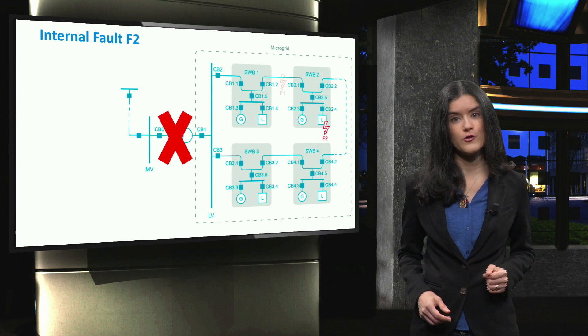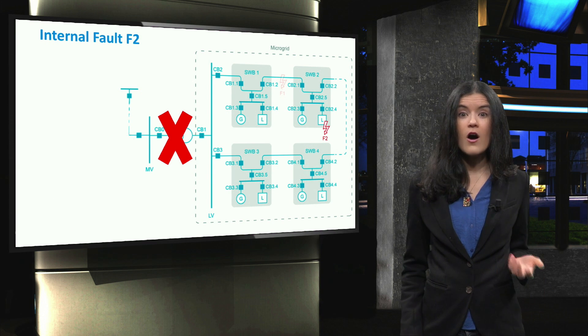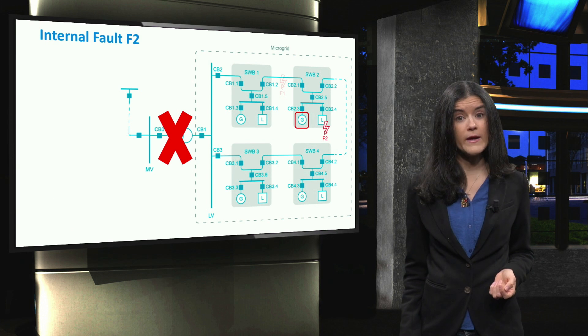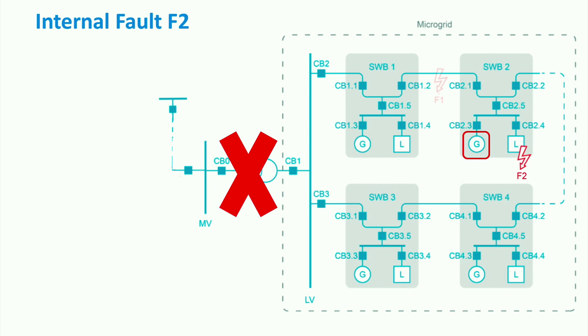If the fault occurs at F2, this would mean that it was caused from the neighboring distributed generators. The settings for CB2.4 are adjusted in such a way that they are just slightly higher than the rated load current of the distributed generators, causing it to trip. If CB2.4 does not trip, then switchboard 2 is isolated by CB2.5 using a directional overcurrent relay. In this case, no sensitivity or selectivity problems are foreseen.